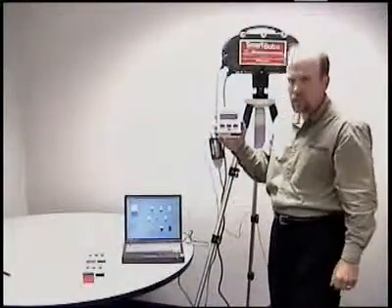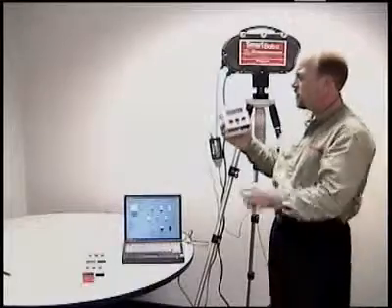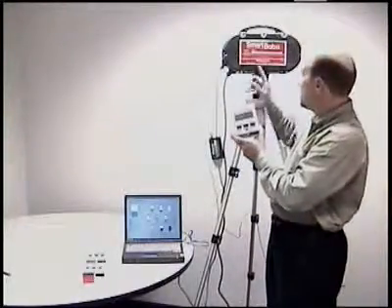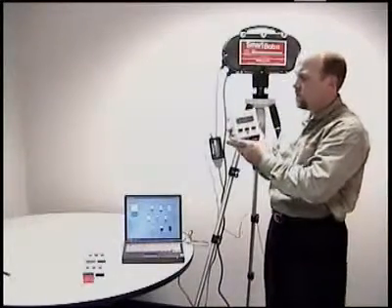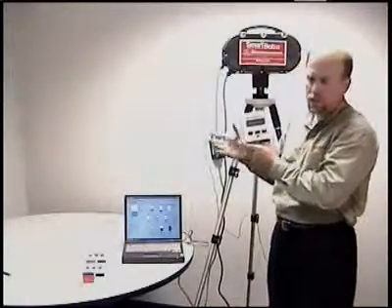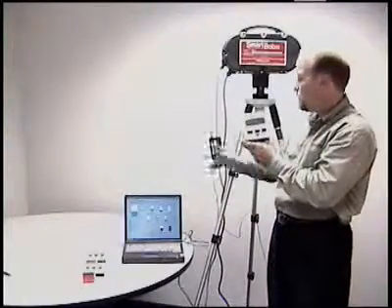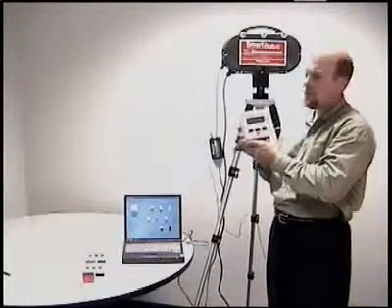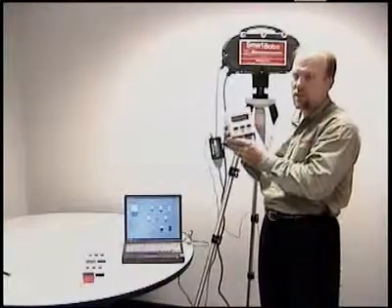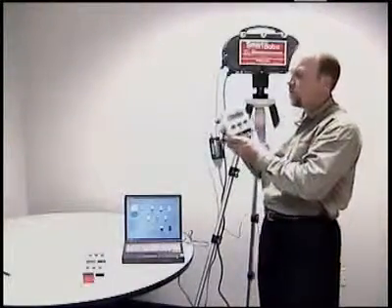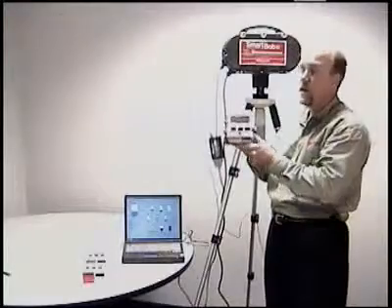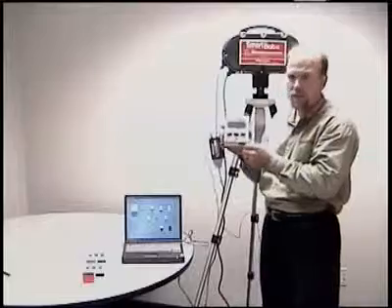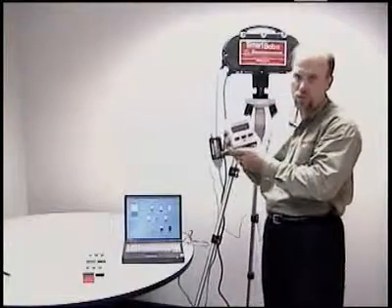Last is the RDU, which is a remote display unit. This is a listening device that is addressed to the individual remote. If we're controlling this with the PC, we initiate the measurement with the PC, and this will give us a remote display of distance of product, distance to product, and percent full of the vessel. If you want to share information with the PLC or DCS, it has a 4 to 20 milliamp output also.